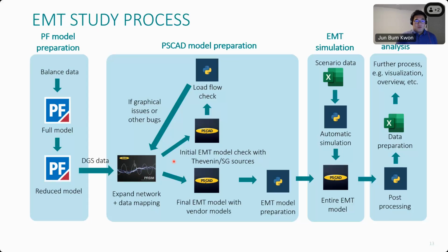So once PRSIM is able to import some new XML file depending on the scenario, then it will be exported to the PSCAD, and we have some internal process for load flow checking. So basically, we need to check the quality of the PSCAD EMT system level model exported from the PRSIMs, to check if they have a good balance compared to power factory load flow. For example, voltage, active power, reactive power, we do such kind of quality check. And then we do some final check with the vendor models.